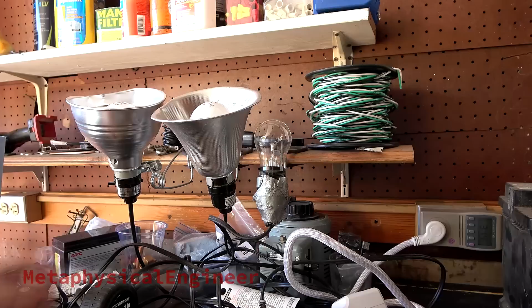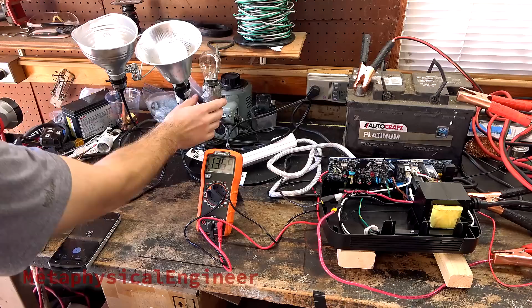With the unit back together enough to power up, I'll connect 3 light bulbs adding up to 120 watts. This equals my computer at low load with 1 monitor running. While worn out, this car battery should still have decent reserve capacity. UPS datasheet claims 21.5 minutes at this output level, so I'll run it for half an hour and see what temps I get.